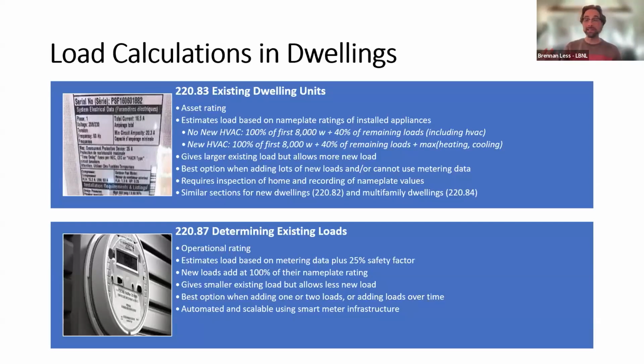You also might get slightly different answers from year to year, where the observed load might be a little higher one year or lower the next for weather reasons or all sorts of reasons. So that's worth knowing. And there, they take the maximum demand, add 25%, and then you can add new loads to that based just on their nameplate rating — there's no 40% adjustment, it just gets added directly.